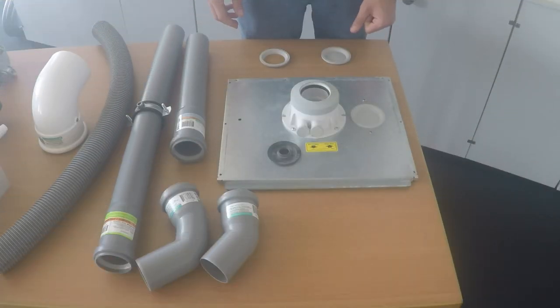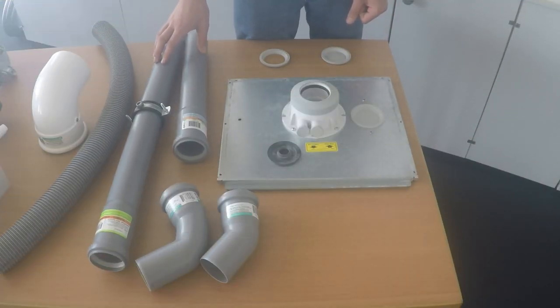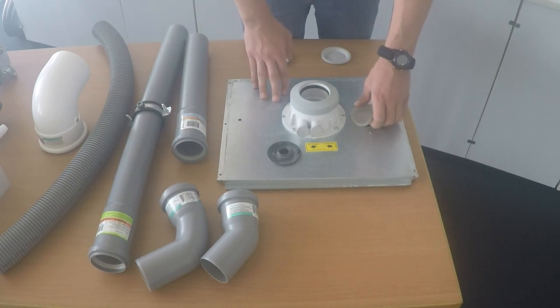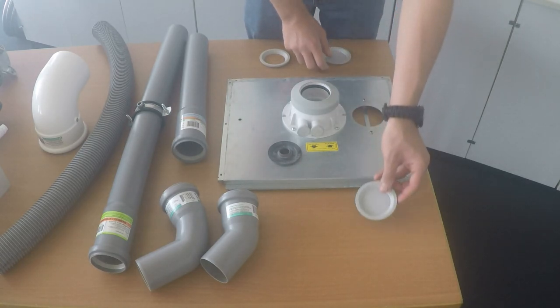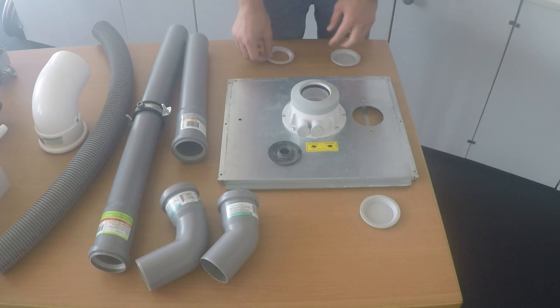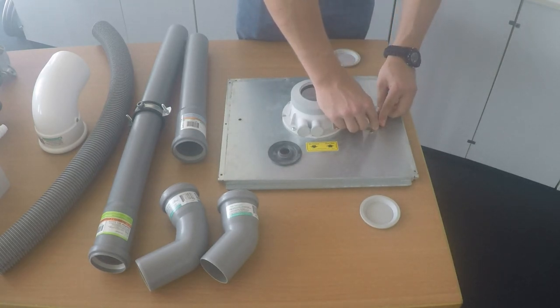The first method that I want to go over is the two pipe method. In order to do this on the boiler, you have to remove this cap and you have to peel out this center portion of the ring like so. And after you do that, you will be left with this open ring, which you will replace in the hole where you found it.